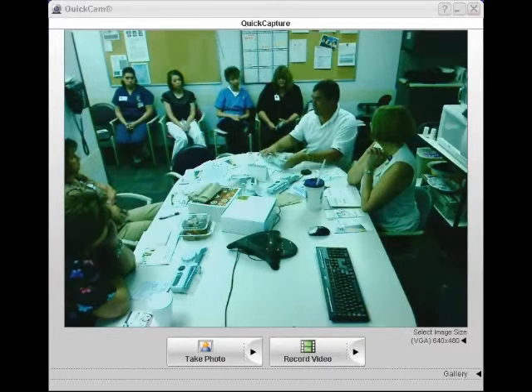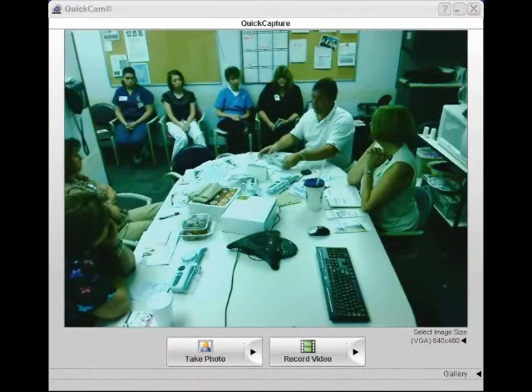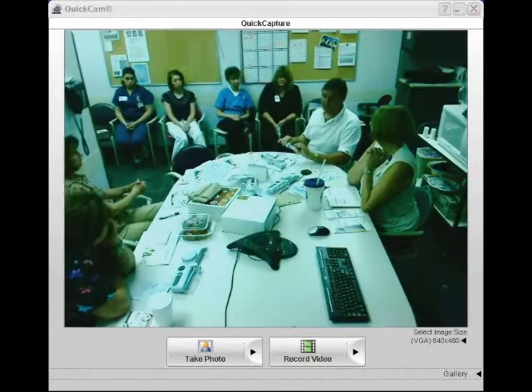This particular pump doesn't have a setting or a control to identify how fast. Typically, you'll start out kind of like IVIG, where you titrate up and then you go faster. Well, in this particular product, you use either a longer tubing, and then you go to a medium-sized tubing, then you go to a shorter tubing.